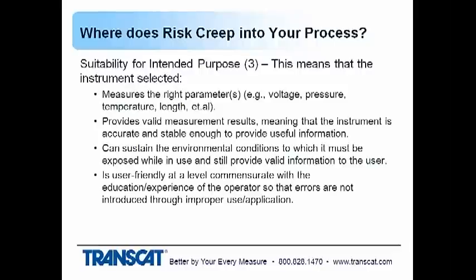So I want to talk about some specific categories here, starting with suitability for intended purpose. Again, when you're selecting an instrument to make measurements in your production process, you've got to look at the parameters that you're measuring in the process and make sure the instrument can measure those same parameters. You also want to make sure that you have a good, accurate product that can make stable measurements for those readings. What environment is it being exposed to? You've got to check that as well as part of the suitability for intended purpose, making sure that the instrument, as stated by the manufacturer, can work in the environments it's being used in, and checking also to see if there's an impact to its accuracy based on the environment that you're exposing it to. And then the other thing is the experience of the operator and their ability to use the instrument properly so that you don't introduce other errors in your measurements.